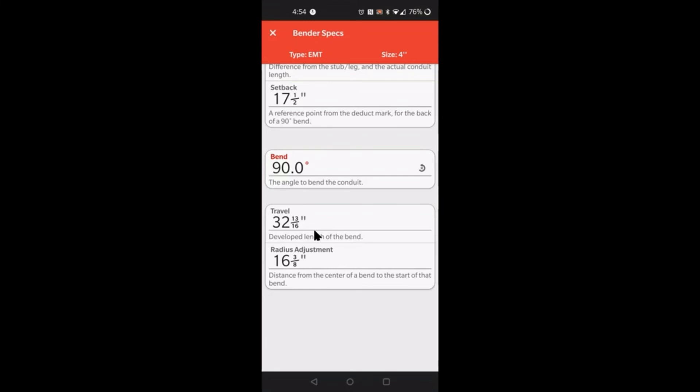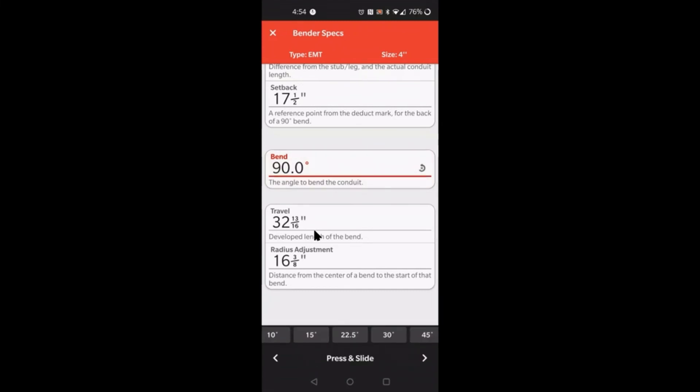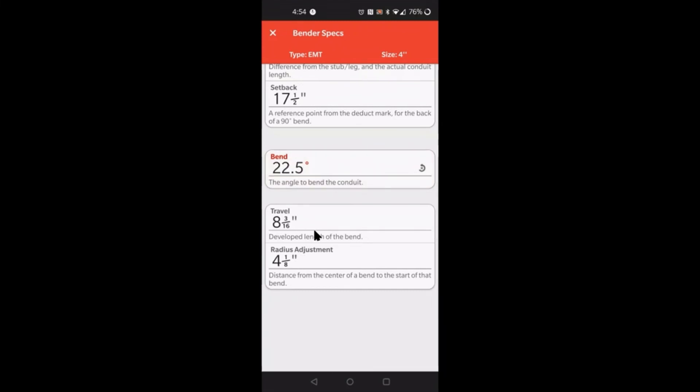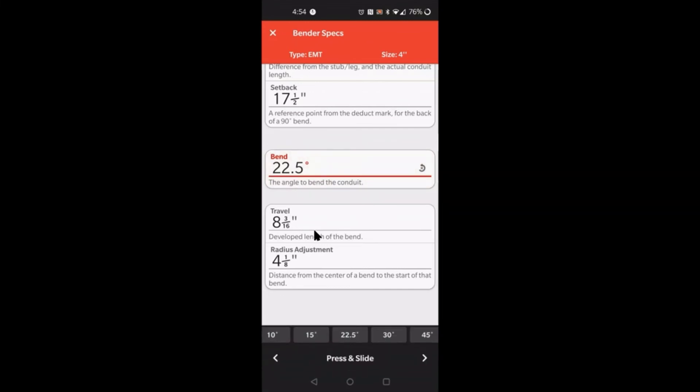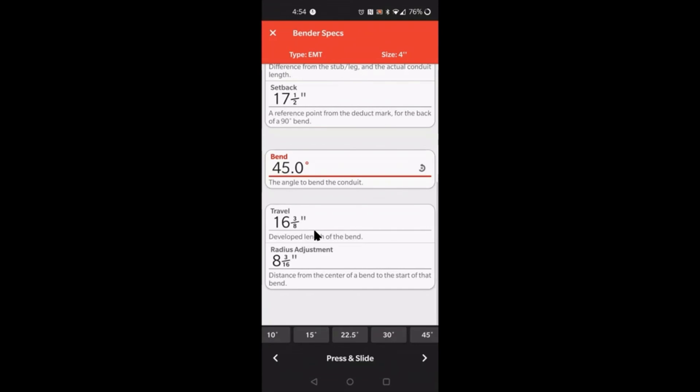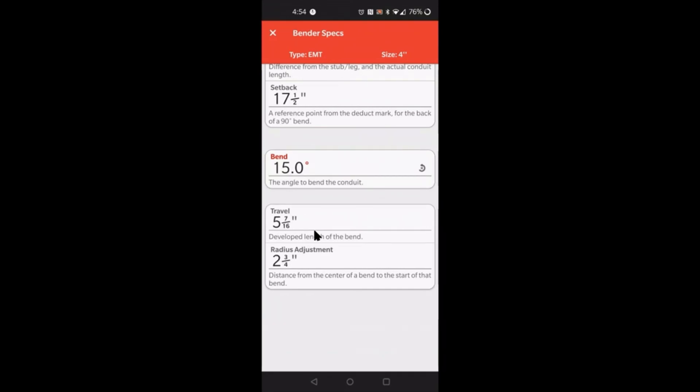What's cool about this is that you can actually change the degree of bend and get the travel and radius adjustment values changes as well. So you can get any of the travels that you want. It's simply there. Let's just say I wanted to do a 15 degree offset and I wanted to know what the radius adjustment is for that. It's two and three quarters.